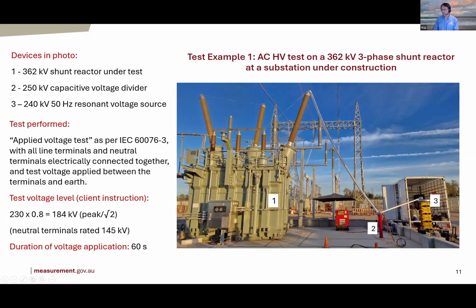So in this particular example, you have an excitation transformer. You have four air core reactors put in series with the excitation. By changing the air gap, you change the inductance, and by varying the inductance, you achieve resonance with the capacitance load, and that's how you generate the voltage. That's very useful, because otherwise you need to carry a gigantic power source, right? Which is not that often available for on-site testing in particular.